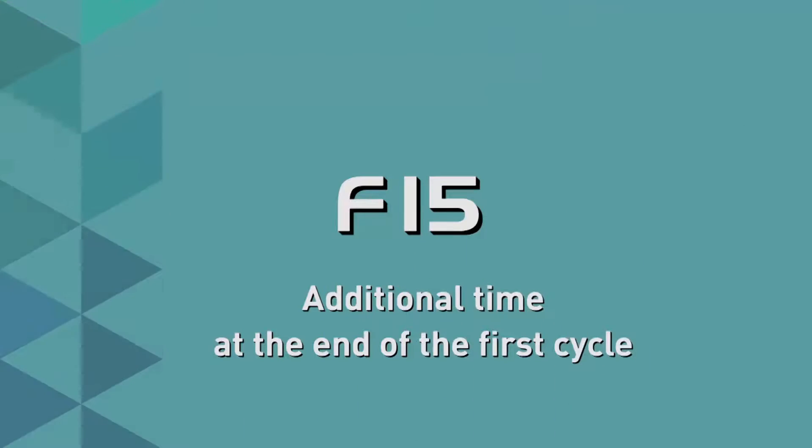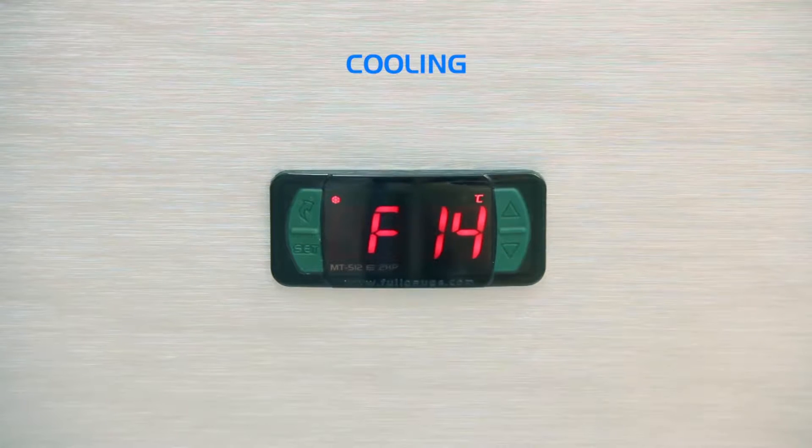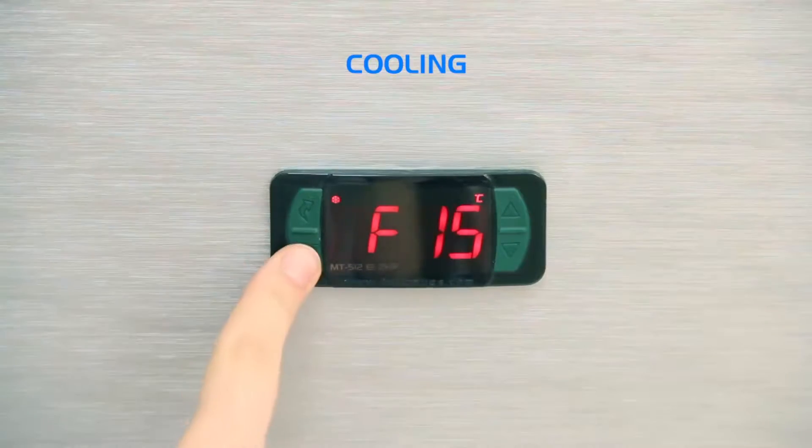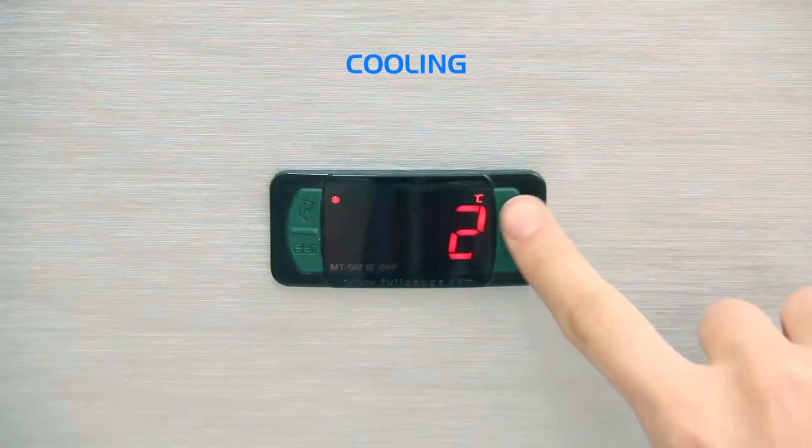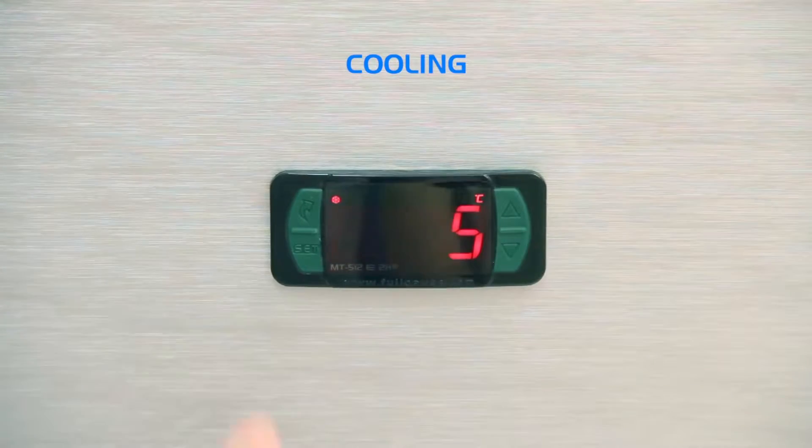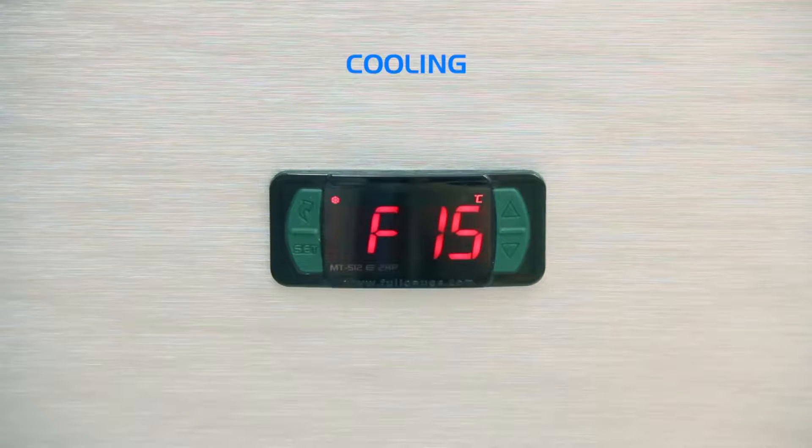F15, Additional Time at the End of the First Cycle. This parameter allows you to increase the cooling time of the first cycle, after driving the controller. If you do not wish to adopt an additional time, select No, or provide a time of 1 to 240 minutes. In the example, we opted for an increase of 5 minutes.